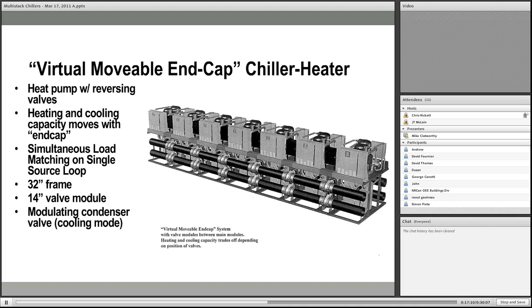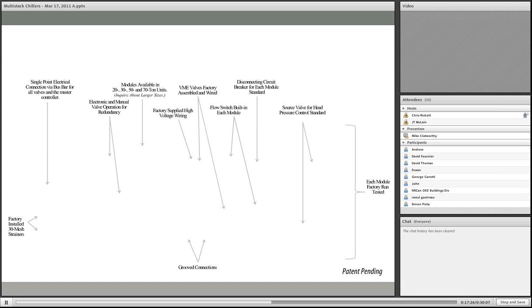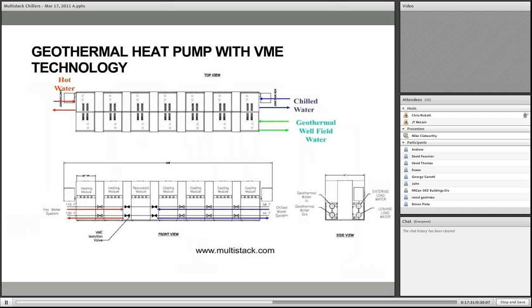This is called virtual movable end cap, and it's a funny name, but what it essentially means is that we can do simultaneous variable heating and cooling on a common source sink. And by closing a set of valves, hopefully you can see my arrow, but by closing the right set of valves, we can reconfigure this chiller on the fly to do simultaneous variable heating and cooling on a common source sink. And this is simply a picture of a system. But what we really want to see is the diagram here.